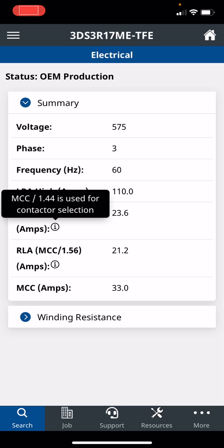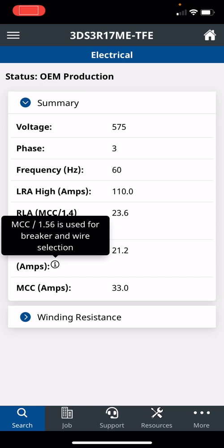You need a 23.6 amp contactor for this compressor. You click on this one, and this one here is for your breaker and wire selection, and they need to handle at least 21.2 amps. The MCC is the maximum continuous current that compressor can run before that internal protector will trip, 33 amps.